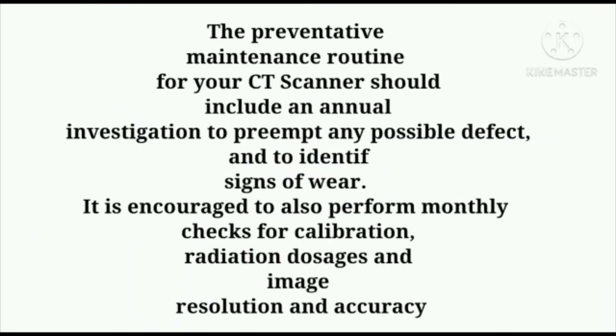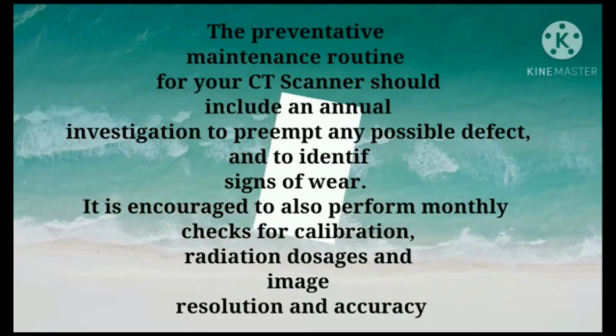The preventive maintenance routine for your CT scanner should include an annual investigation to prevent any possible defect and to identify signs of wear. It's encouraged to also perform monthly checks for your calibration, radiation dosage, and image resolution and accuracy.